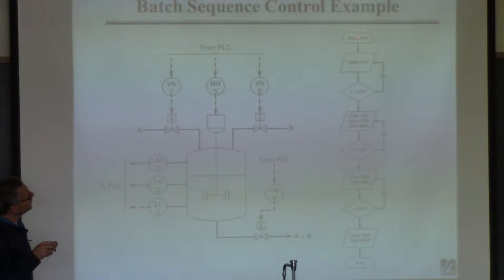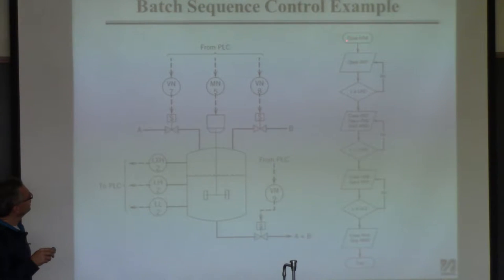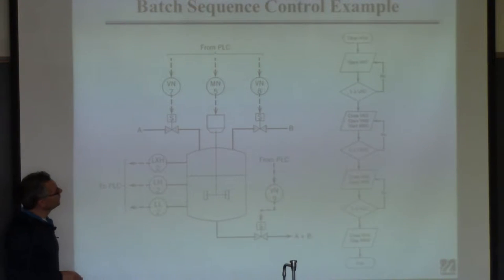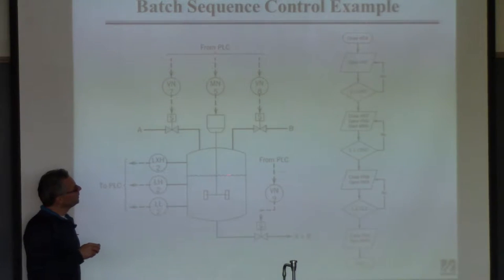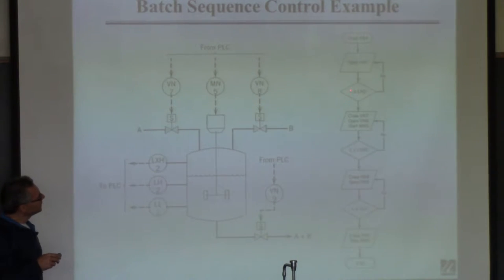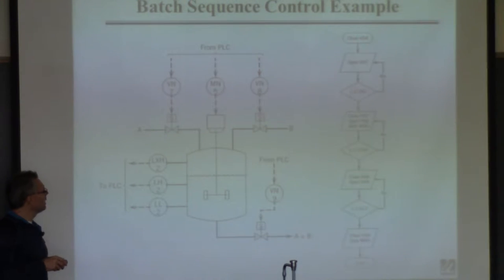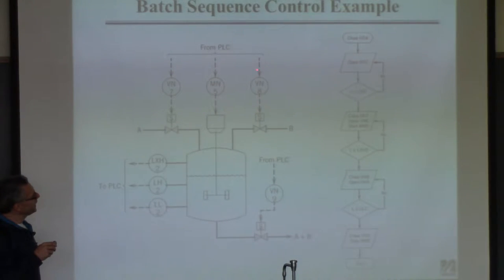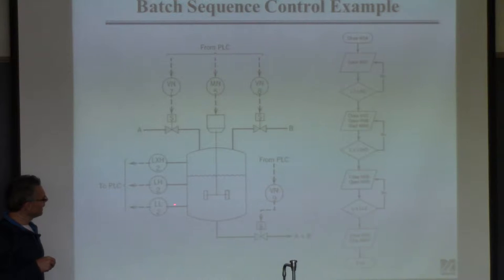Here's how this would be used. First, open the valve and feed in reactant A until the level reaches the low level point. Once the level reaches that point, close this valve, open the next valve, and start mixing. Then keep adding component B until the level gets to the extra high point. Once the level reaches that point, close the inlet and open the outlet, draining the tank until the level drops below the low level. Then close that valve and stop mixing.